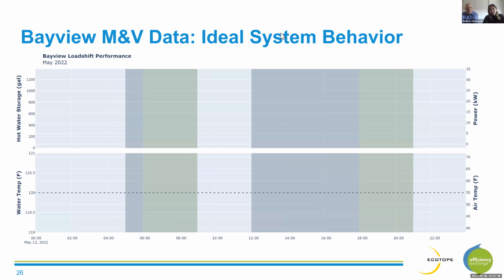And the first thing I want to draw your attention to is the background colors of the plots. These indicate the control sequences that were sent to the heat pump. So we have blue for load up. This is when we're charging up the tank, and then green for shed when we are trying to keep the heat pump off. So on this particular control sequence, we have a load up period from 5 to 6 a.m., followed by a 3-hour shed from 6 to 9 a.m. with a little bit of a break, and then we begin loading up at noon for our evening shed period, where we shed again from 6 to 9 p.m.